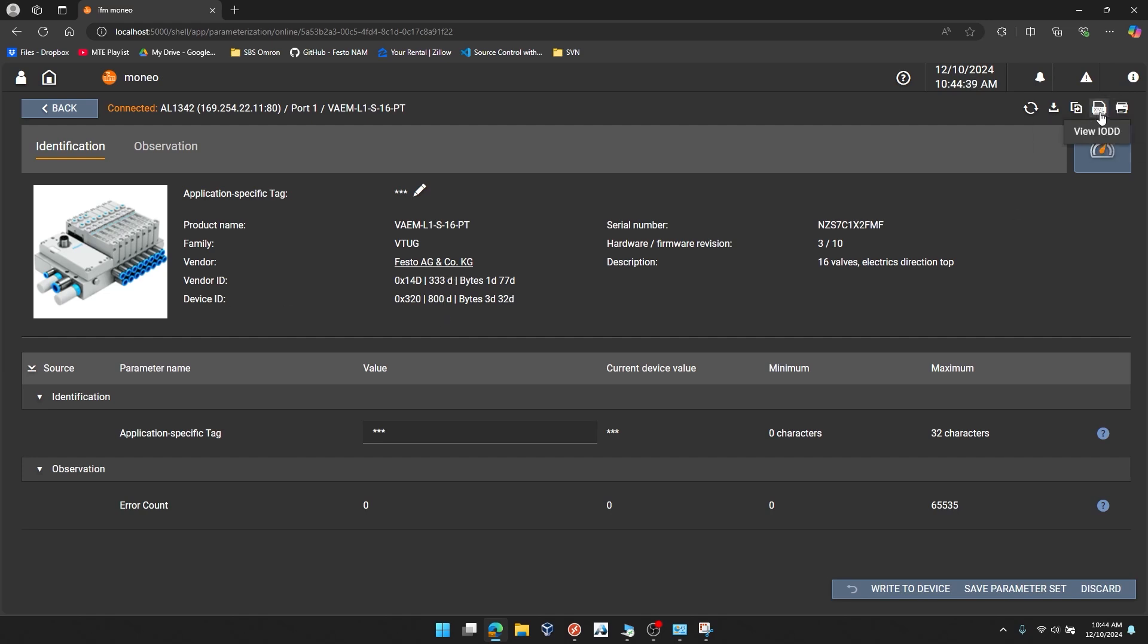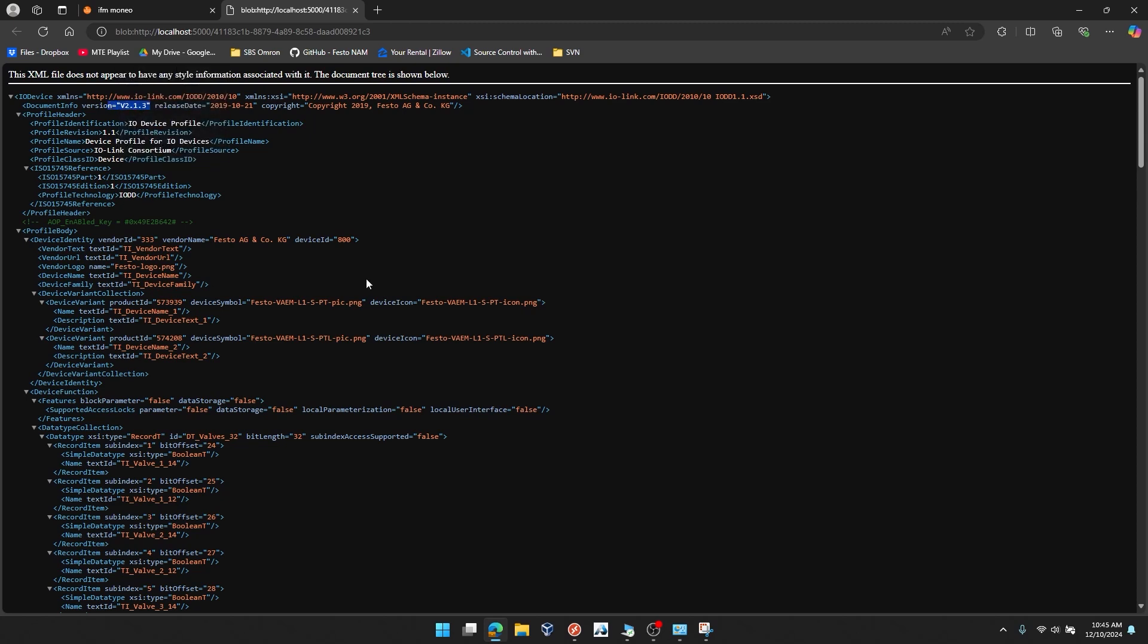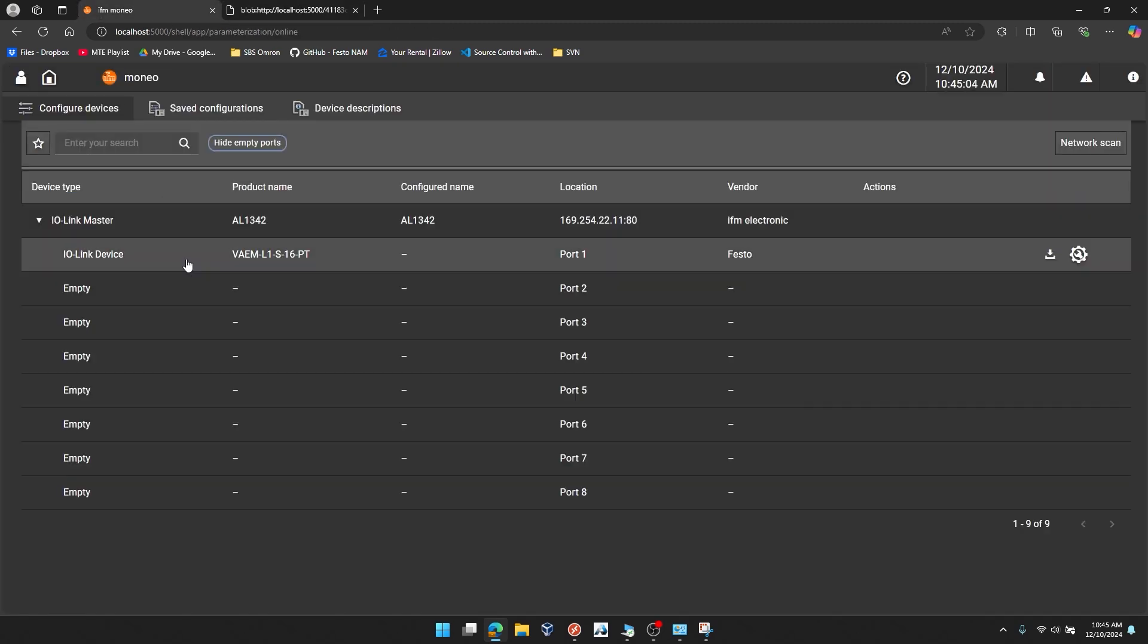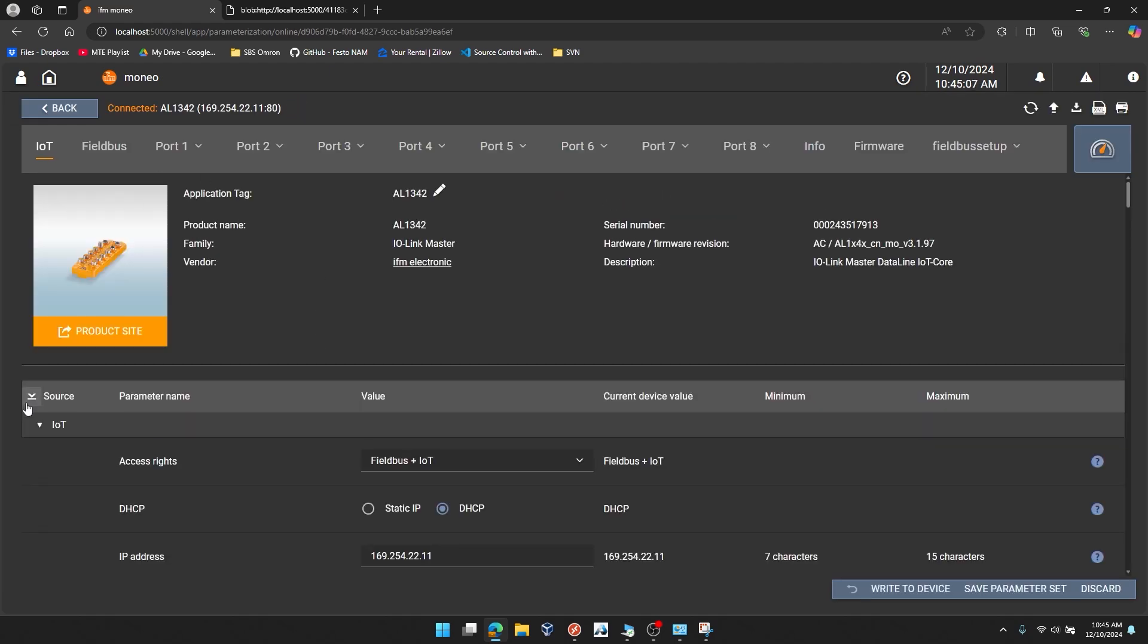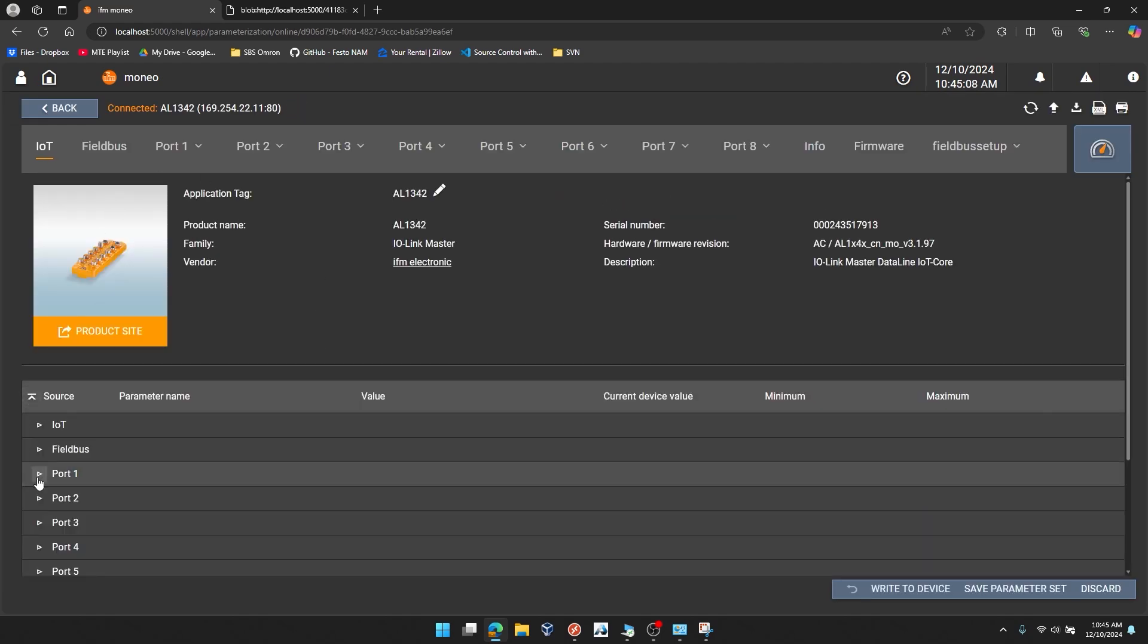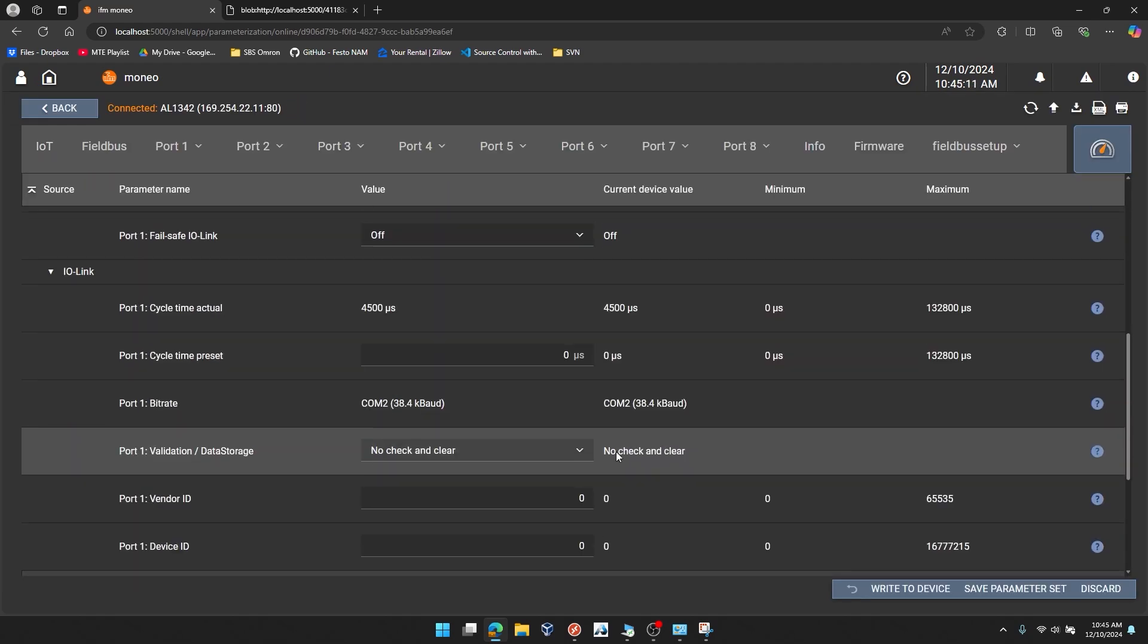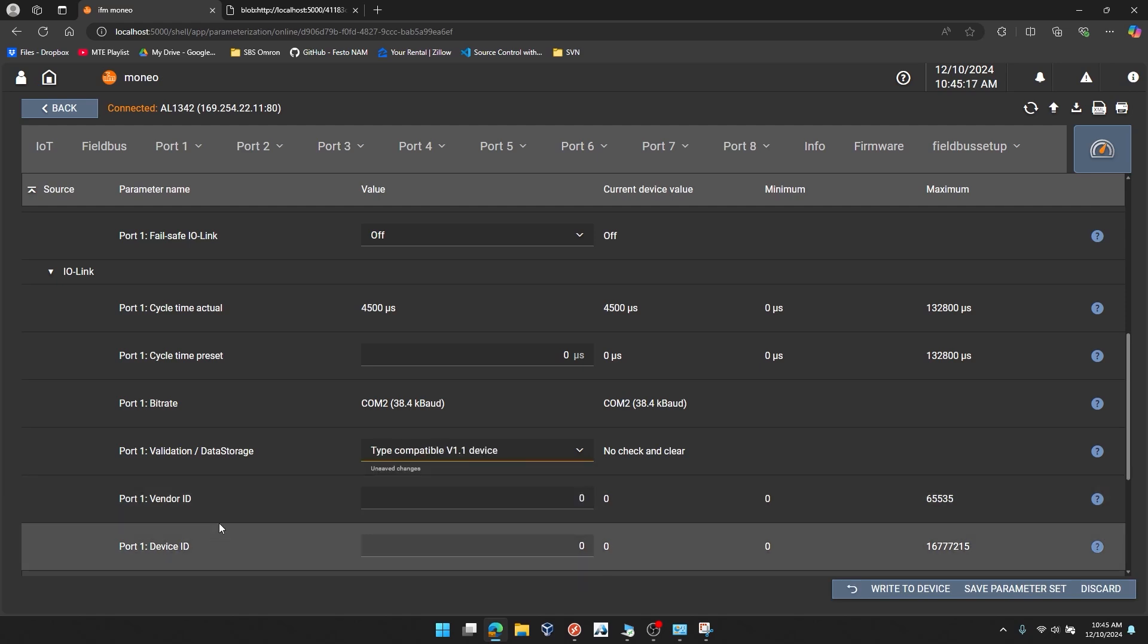But I can actually click view IODD. If I look in the XML file, this is your IO-Link description file, profile revision. You can see right here that it says .1.1. That's going to be your IO-Link 1.1 version. Don't get confused by the version shown up here. This is the version of the IO-DD file v2.1.3. So now we'll go back to our IO-Link master. Again, we're going to go down to port 1's IO-Link settings. And now that we know we're definitely in IO-Link version 1.1 device, we'll make this selection.